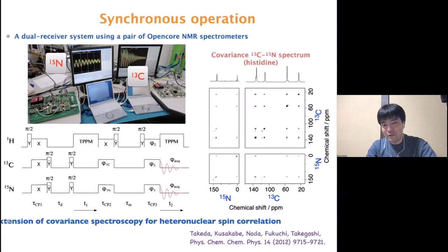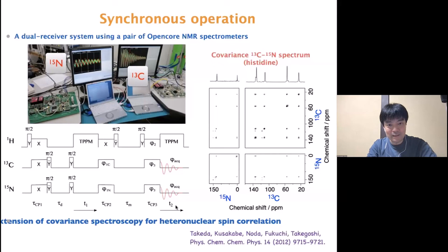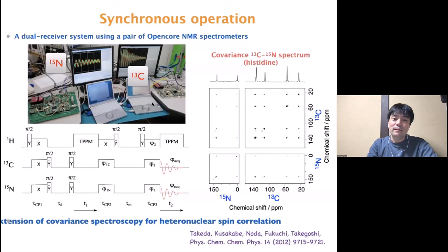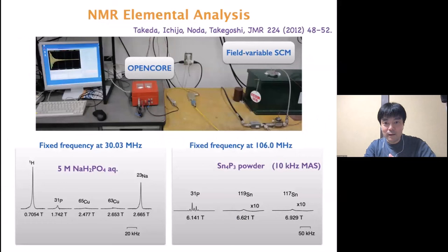When we want simultaneous acquisition of multiple channels — for example, carbon and nitrogen signals simultaneously — our spectrometer has only a single receiver channel. But a pair of separate spectrometers can synchronize with each other using trigger signals, allowing us to simultaneously acquire carbon-13 and nitrogen-15 signals.